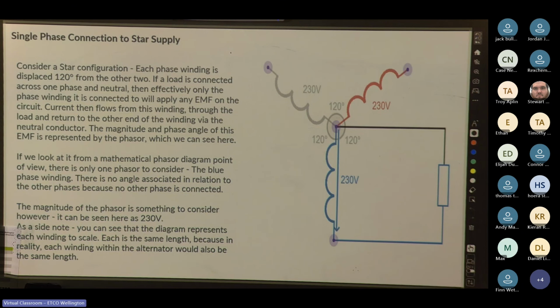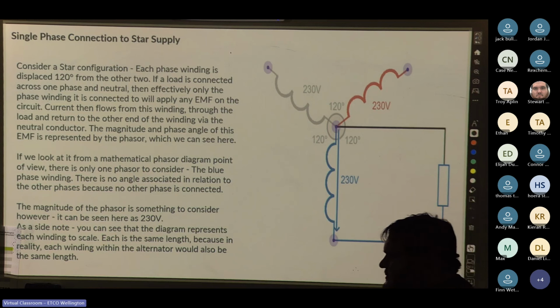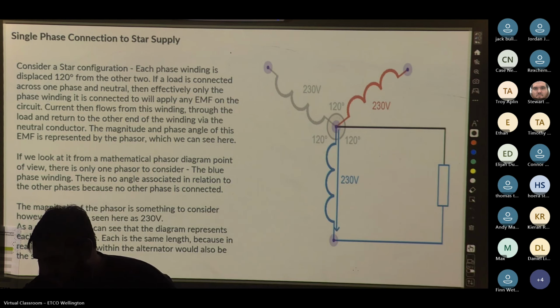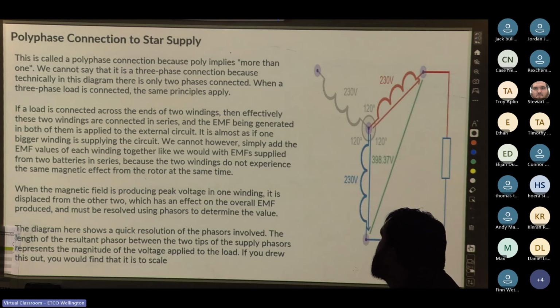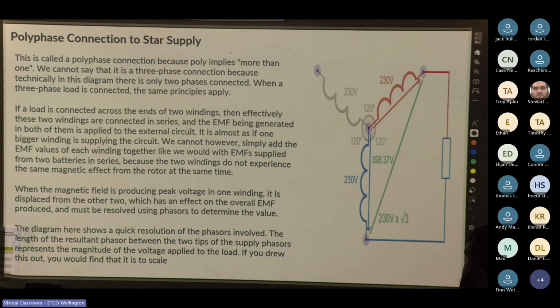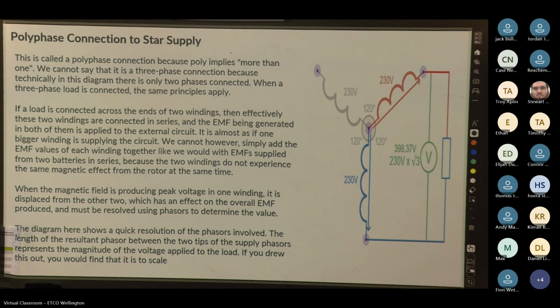The magnitude of the phasor is 230 volts. You can see each winding is to scale, each is the same length, because each winding within the alternator would be the same length. So that's single phase, and this is polyphase, or two phase. If we measure between phases, we get 398.37 volts, which is 230 volts times the square root of 3. We'll look at that in a little bit.